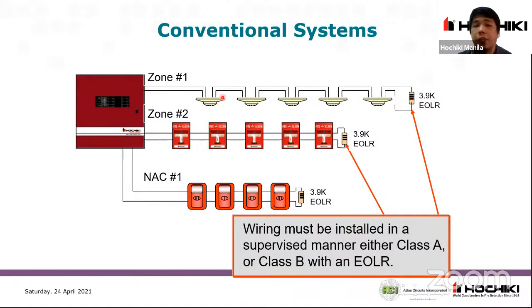So in terms of operation, ayan. So sa operation ng conventional natin, wiring must be installed in a supervised manner, either class A or class B with an end-of-line resistor. So pag conventional natin, ang practice is usually class B. So pag class B tayo, yung diniscuss natin kanina, we must have this end-of-line resistor doon sa last device to have a full supervision of the zone. So kapag hindi nyo nilagay sa last device, hindi siya magkakaroon ng full supervision. Okay? So take note again, hindi dapat tayo nagkakaroon ng T-tapping kapag conventional na class B tayo since hindi siya magkakaroon ng supervision.